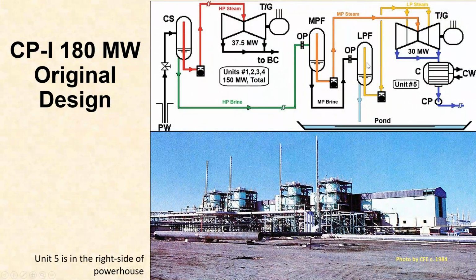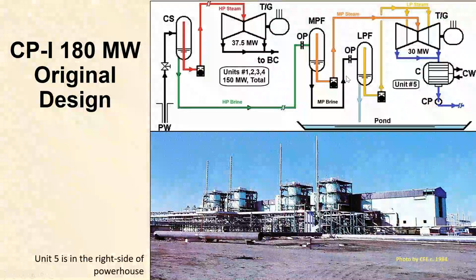But when 1981 came along and they put in the lower pressure unit, which turns out to be a double flash unit, they were able to use that brine and generate 30 megawatts more without additional wells. This is a smart move, and perhaps this was the first time that this had been tried at a power plant. And it is a standard way now of capturing as much energy as you can from the brine by using bottoming cycles. Fairly standard. This number 5 unit, however, used a low-level condenser, so you don't see one of the barometric condensers outside this unit, because the condenser is beneath the turbine, buried. Next slide, please.